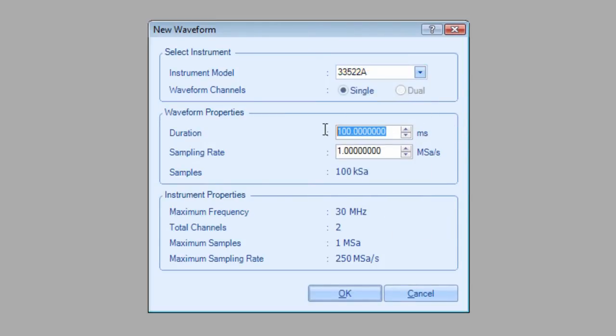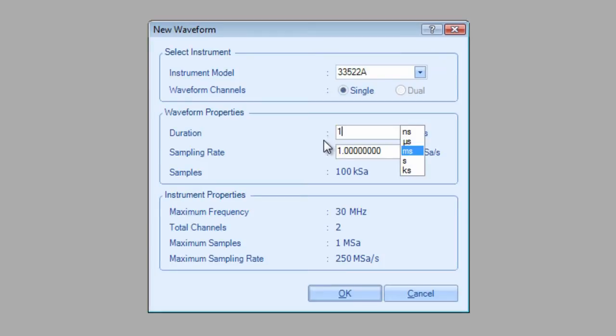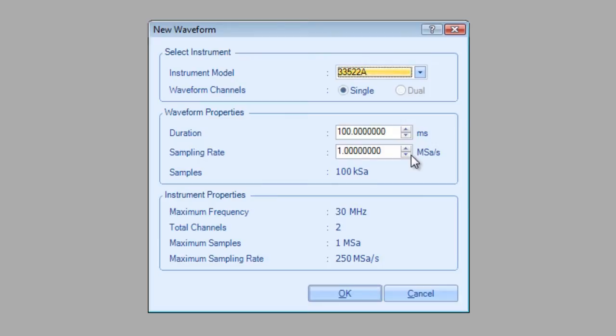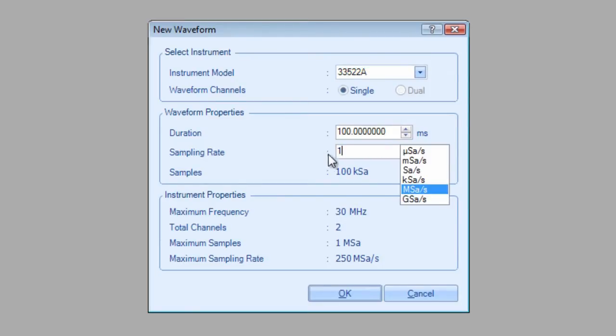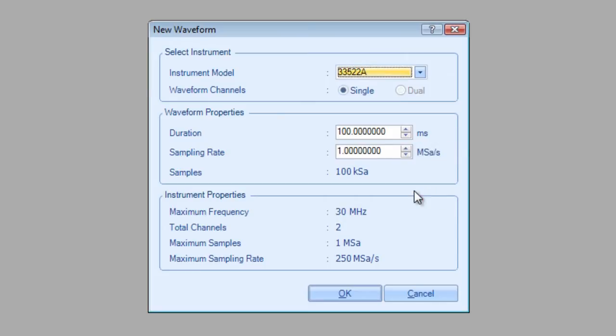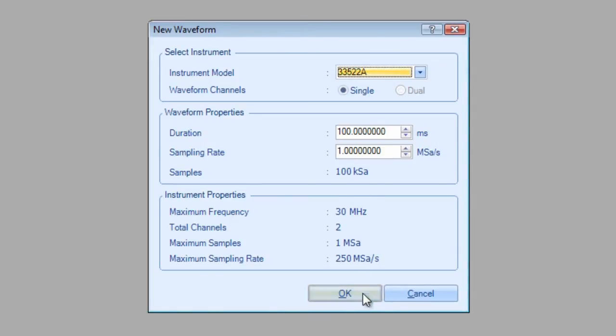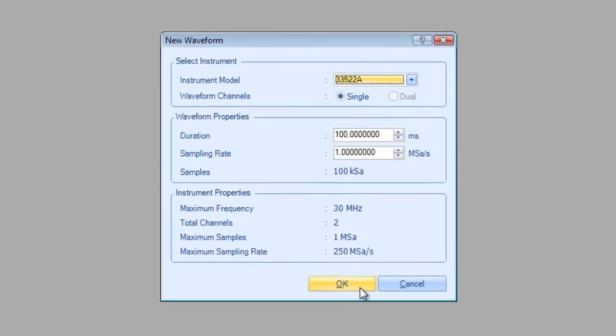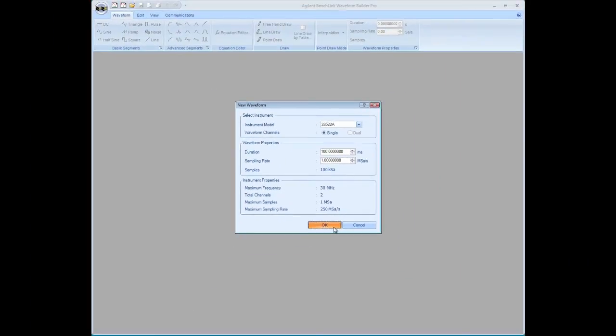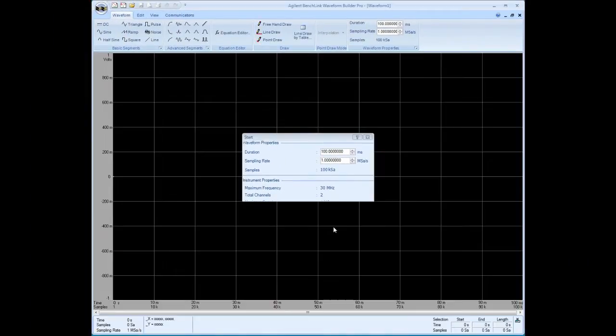Then we have a choice now of setting up some waveform parameters. I'm going to just pick a 100 millisecond duration for this waveform. And let's select a sampling rate of 1 megasample per second. And that will give us 100 kilosample points to work with as we create our waveform. So I hit OK.